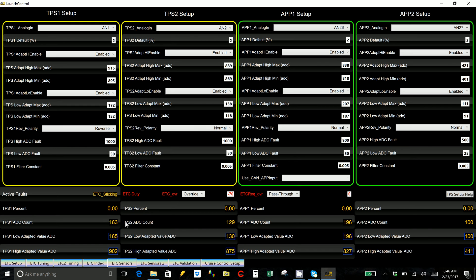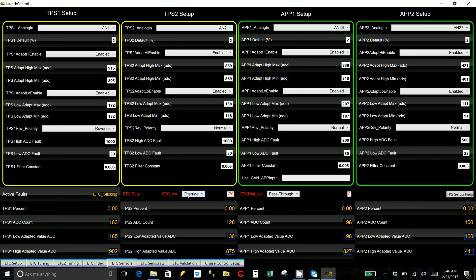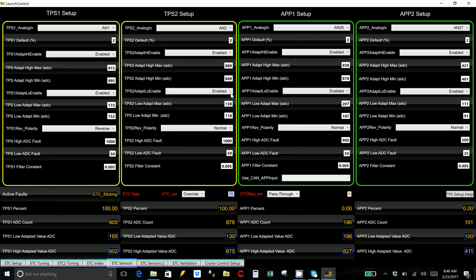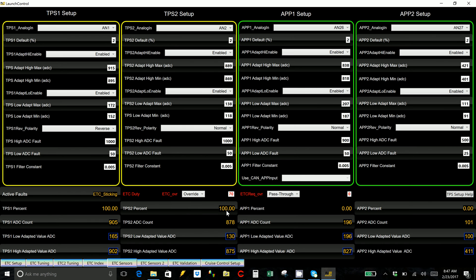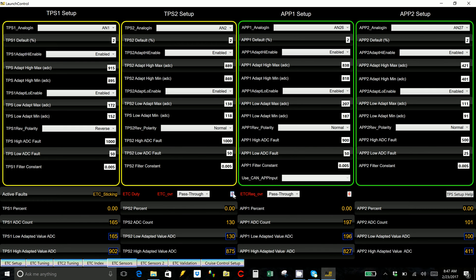So now that we're forcing this thing closed, we're going to check it again. And of course, we've captured 165, we've captured 130. That all looks good so far. Make sure that we're plus or minus 10 on our low side capture, plus or minus 10 on our low side capture here. That's all looks good. Then I'm going to come in here and I'm going to do the opposite. I'm going to open it. So now you'll be capturing 905. Again, that's good. We looked on here, where we captured 902 when we closed it last, 878 to 875, plus or minus 10 up here. So our ranges for the sensors are good. So when I turn this override off, so once you click that off, then the output is not used anymore. So pass through. And then this number here, you don't necessarily have to change that, but I like to put it back to zero. So now you'll see that my throttles are all going to 100% and they're all going to zero. That's exactly what we want. So that's all looks good.